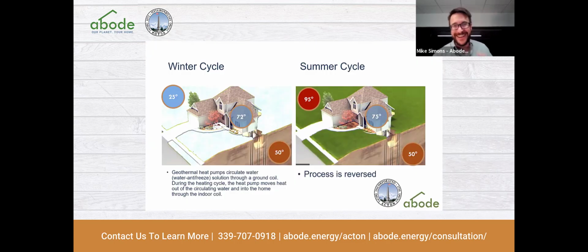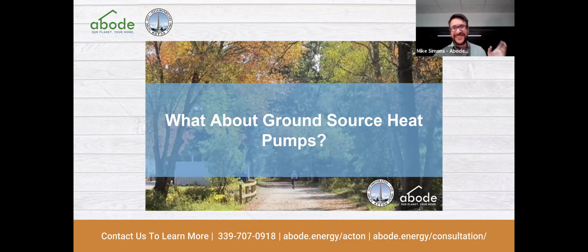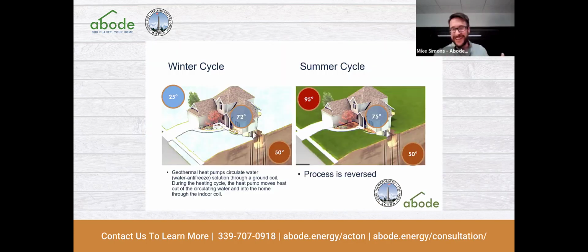So we're finally on to ground source heat pumps. Pretty much everything I said about air source heat pumps is true, but there's one huge difference. I'll give you all the reasons why ground source heat pump people are ground source heat pump people and not air source heat pump people. The fact is, let's say it's 0 degrees outside and you have that negative 15-degree coil, it's only pulling in a delta of 15.